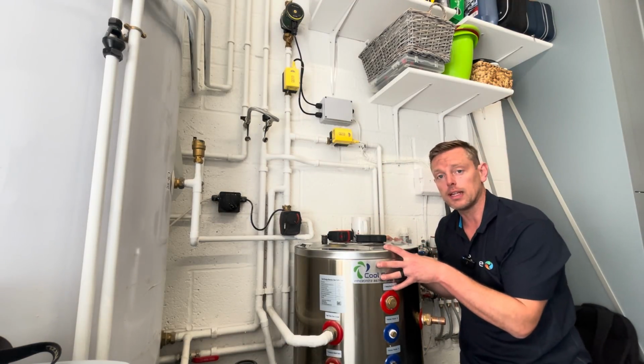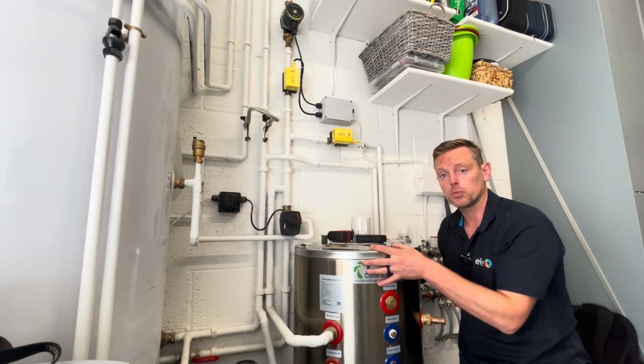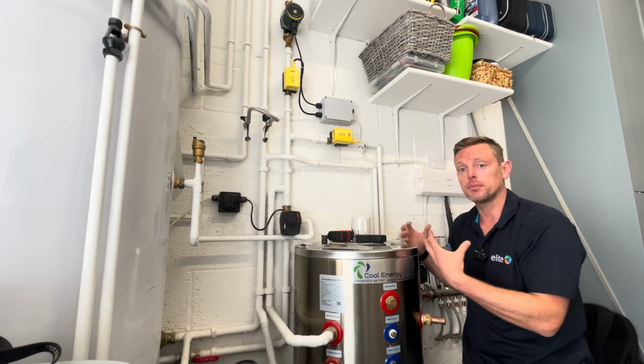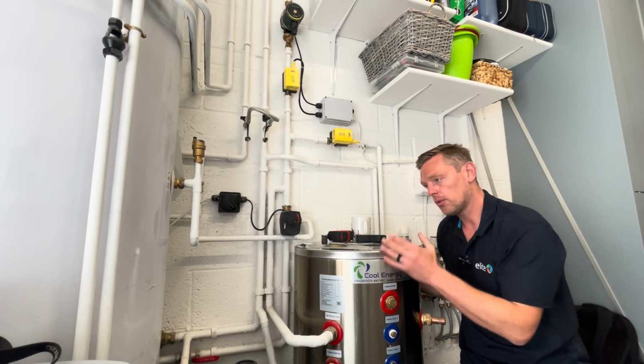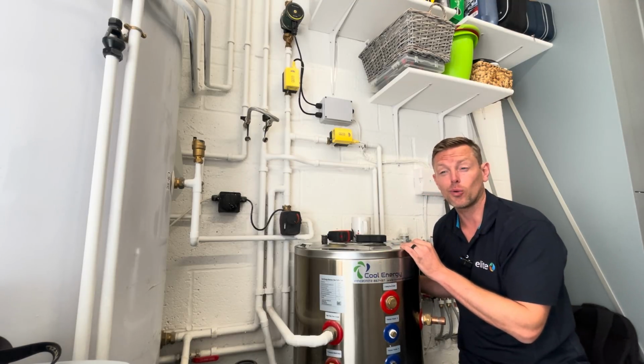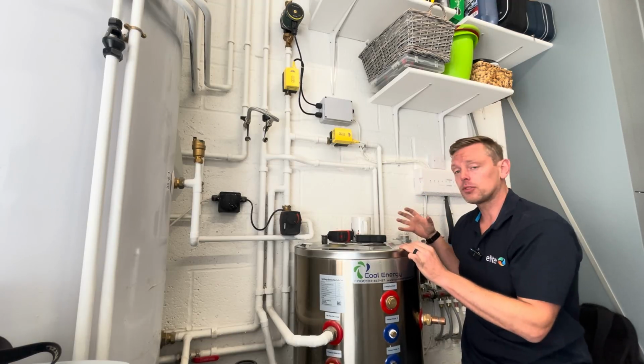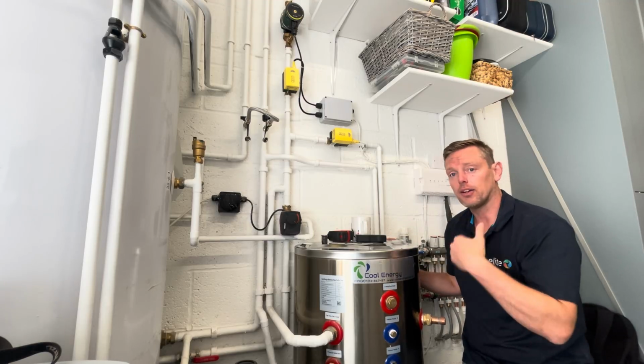They're heating this for no reason. This will heat up really quickly and go back to the heat pump as well and turn the heat pump off quicker because it's not getting pushed into the house and absorbed by the house. It's just going around this. This is really well insulated, going back to the heat pump, turning that on and off even quicker. So the set-up is really high. It's not allowed to go back into the house because of the underfloor and because of this. So it's just cycling all the time.